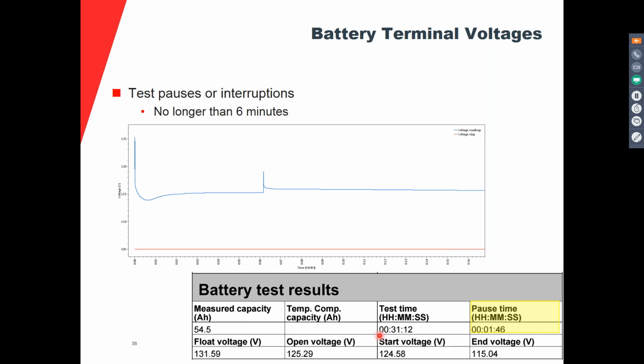When you pause the test, the battery is going to rest, and it's going to recover a little bit of the voltage, and basically it's recovering a little bit of the capacity. So if you pause the test for a long time, you're going to affect your result, and it's not going to be an accurate result. That's why the pause is monitored. In this result, we can see that the test was paused for almost 2 minutes, and you can see the effect of that here. Just with 2 minutes, the voltage went higher, and it takes a while to return to the previous voltage. So it's extending the time that the battery can run, which means it is increasing the capacity of the battery.